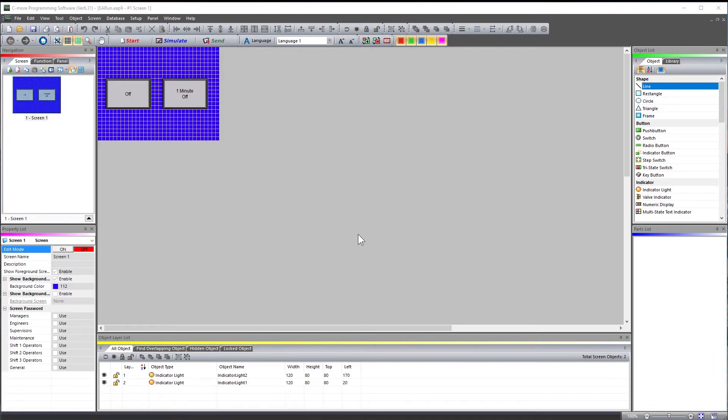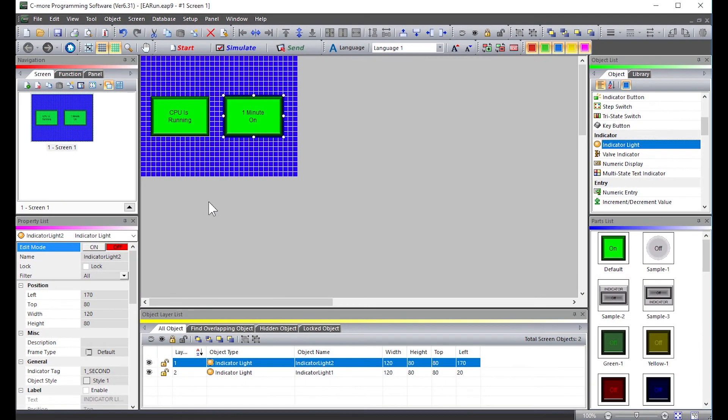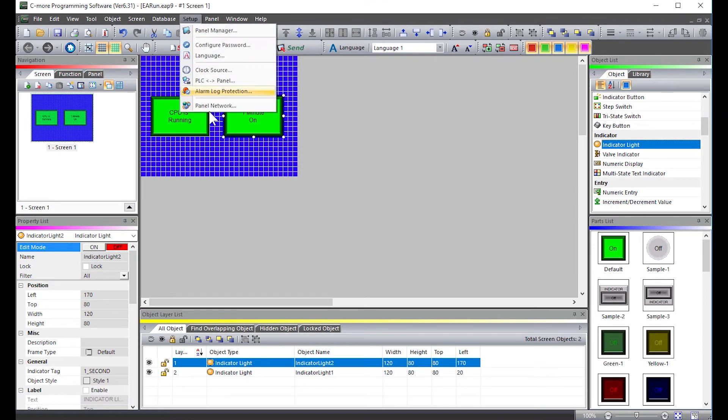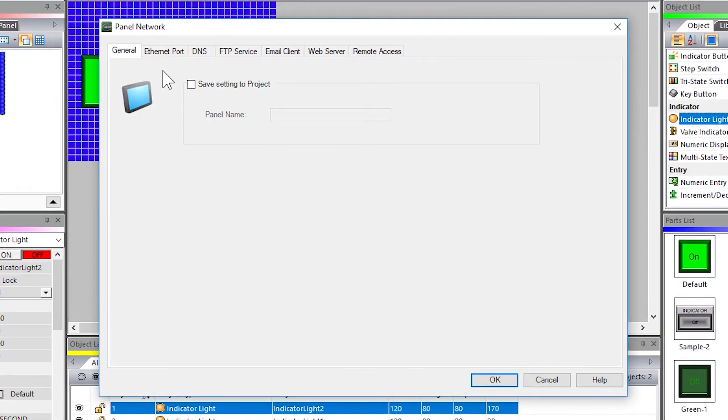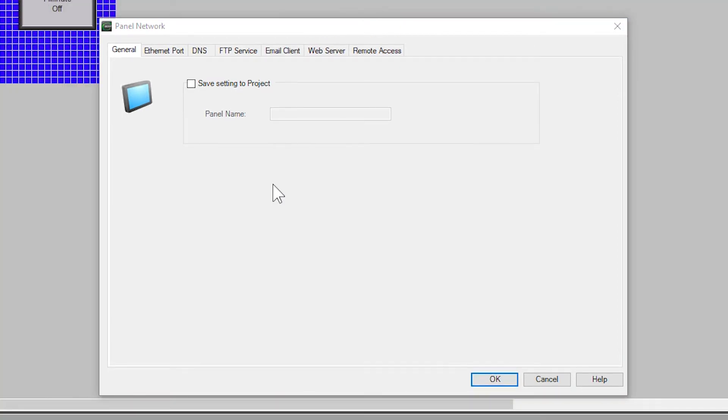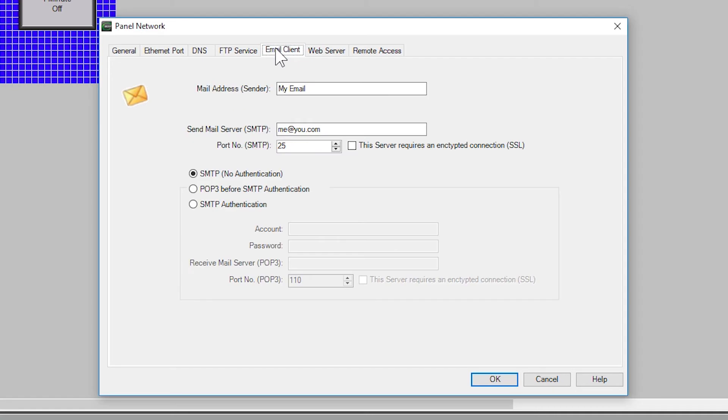Let's go one step farther here and show remotely viewing the panel with the remote access feature. In the C-more panel to turn on the remote access in your project, go to Setup and then Panel Network. To turn on remote access there are two parts to this. We must first turn on the web server and then activate the remote access. While we are here, if you are emailing alarms through your HMI, we must allow internet access with the VPN router. This can be found in the dashboard under Configuration.